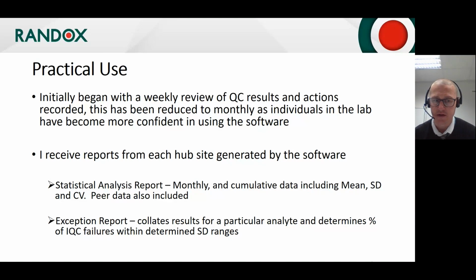So we evaluated and determined that you are going to get some failed QC results. Things do happen, you do get random events. So we worked on a limit of 10%. So anything that shows greater than 3SD results over 10% of the tests of the month, then we'd have a look at that in a bit more detail and determine whether anything's going wrong or whether it is just random error and due to reagent lot changes, calibrations, temperature, mechanical errors, everything that you normally expect in your laboratory.